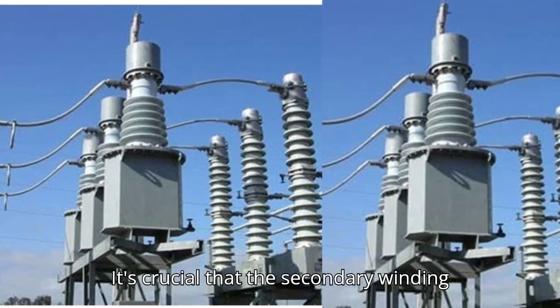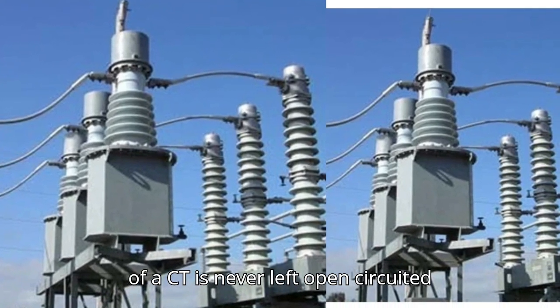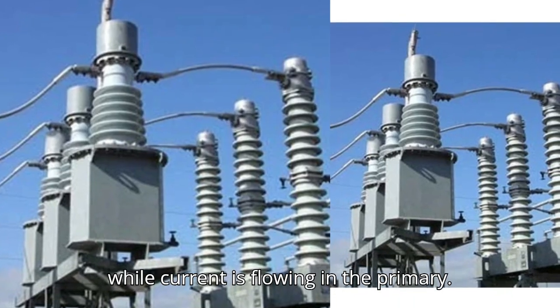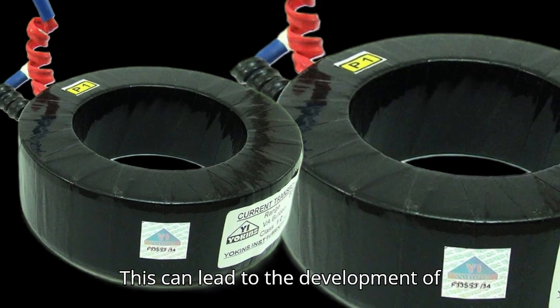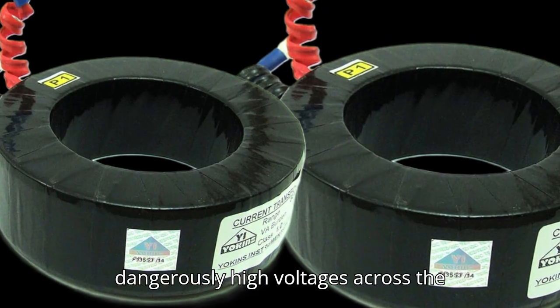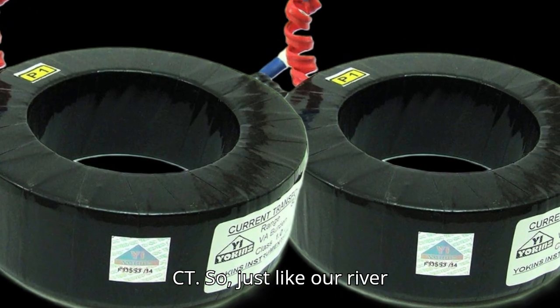The secondary must be loaded. It's crucial that the secondary winding of a CT is never left open-circuited while current is flowing in the primary. This can lead to dangerously high voltages across the secondary terminals and can damage the CT.